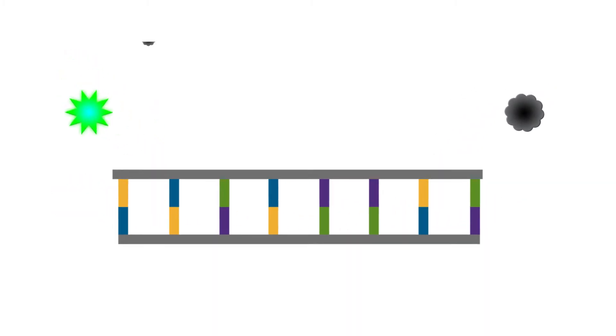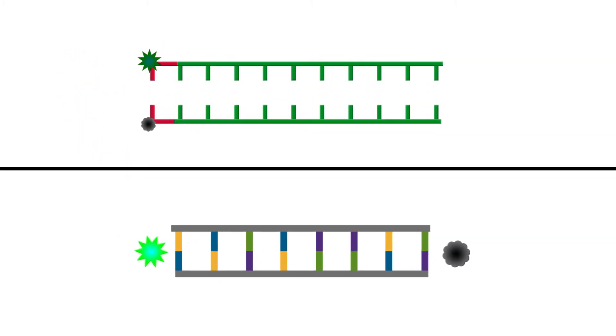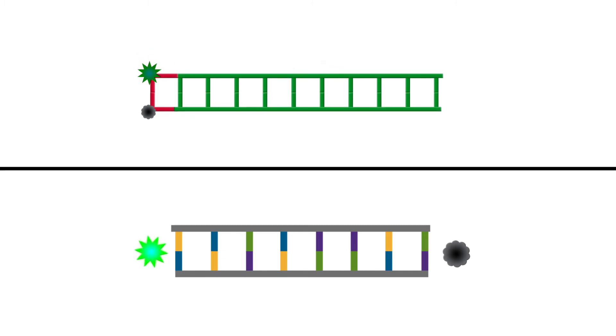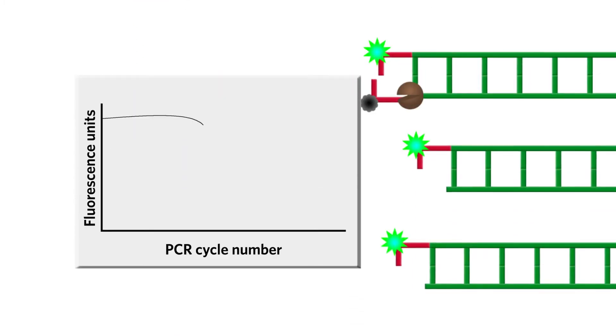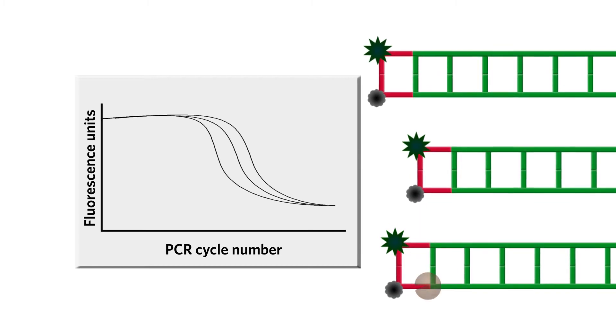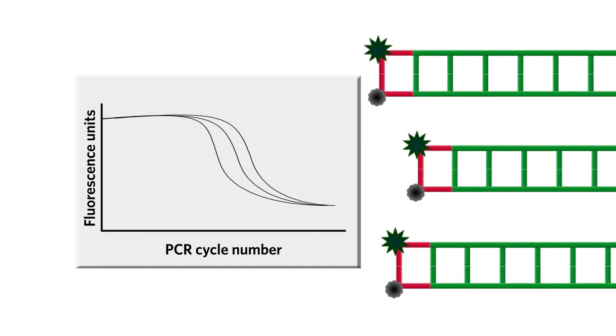The way the reporter and quencher are used in Multicode means a probe is not required and a decrease in fluorescence is looked for instead of an increase. The decrease in fluorescence, with the incorporation of more and more iso-C and iso-G pairs, is directly proportional to the amount of amplicon.